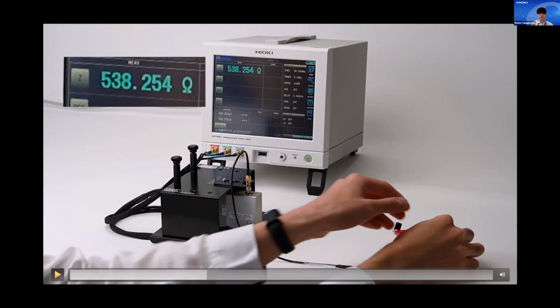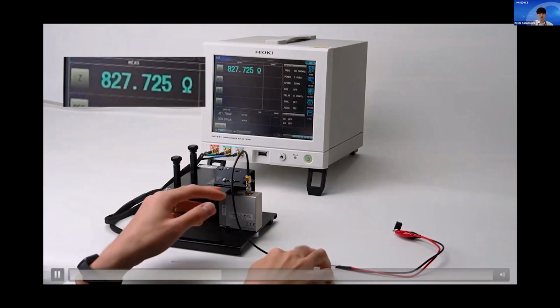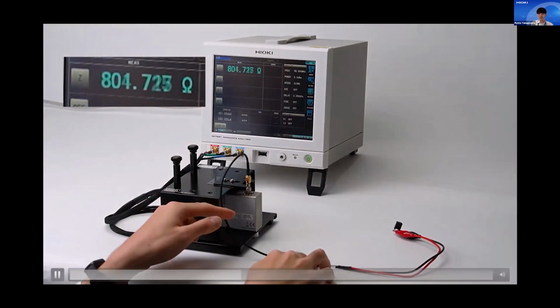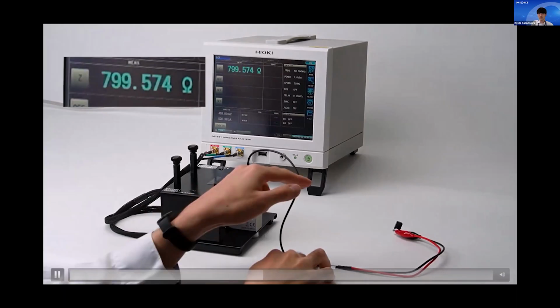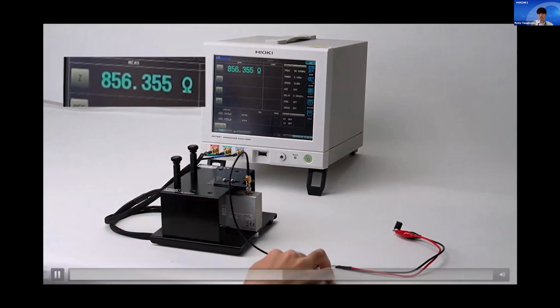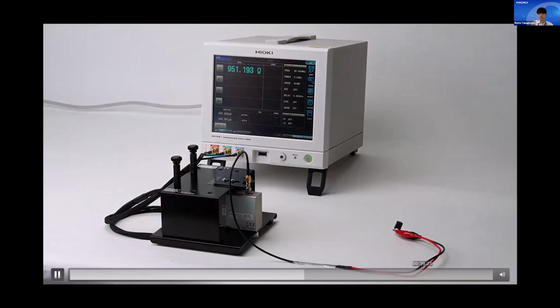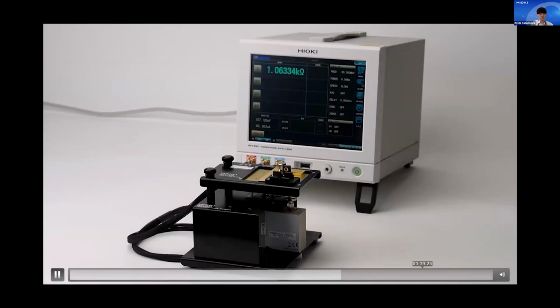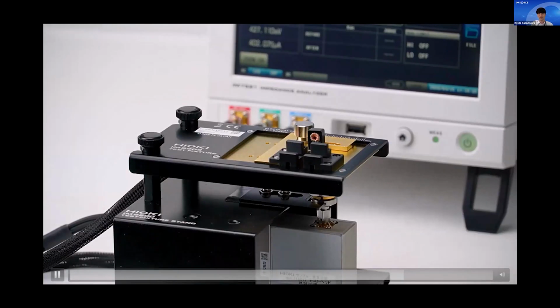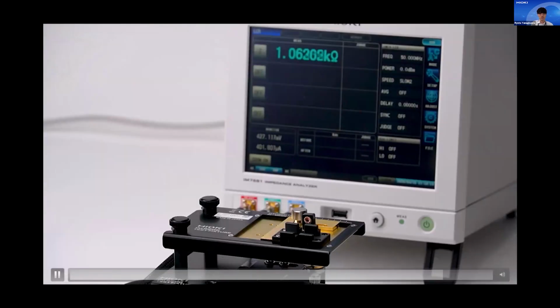Okay, so next, I move like this. The variation is smaller in the coaxial section, but some fluctuation still remains. For high frequency measurement, please use fixtures or RF cables. Like this, the measurement is stable using these fixtures because the transmission line is stable.